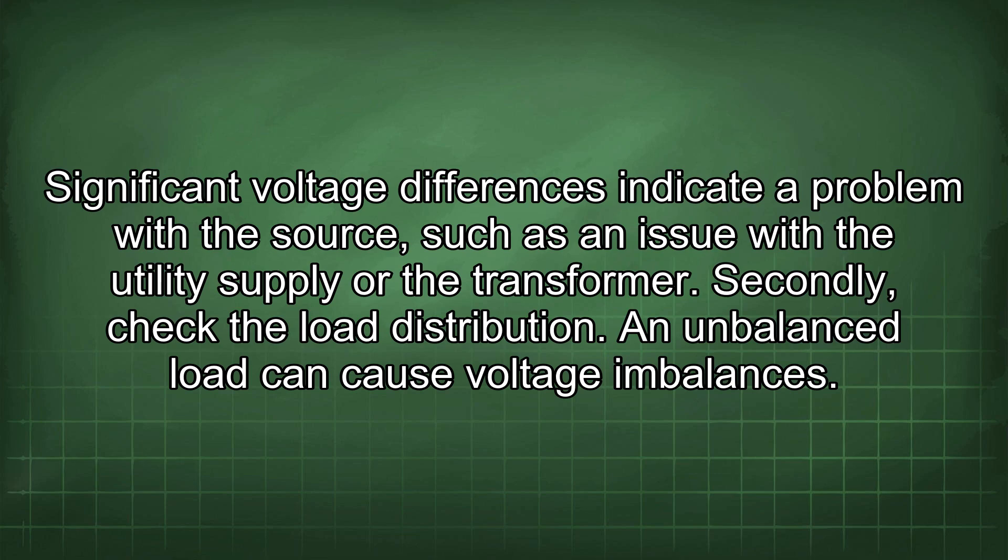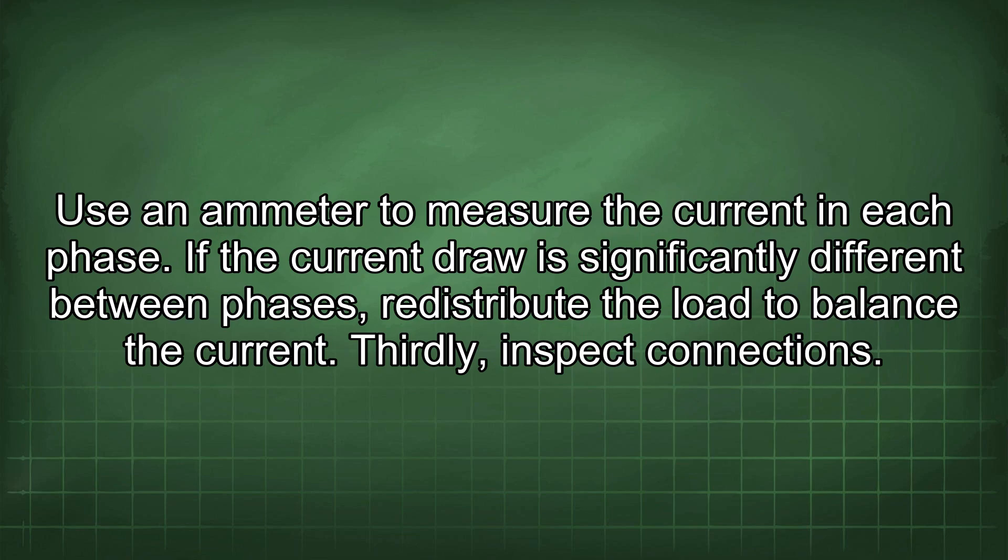Second, check the load distribution. An unbalanced load can cause voltage imbalances. Use an ammeter to measure the current in each phase. If the current draw is significantly different between phases, redistribute the load to balance the current.